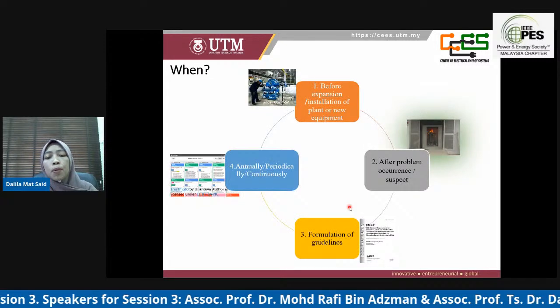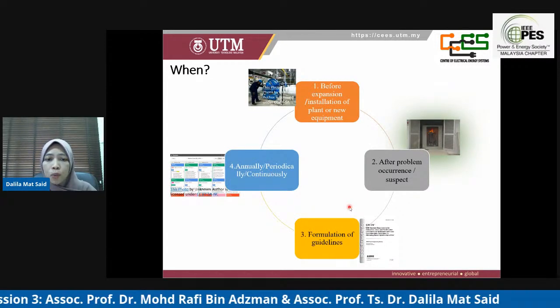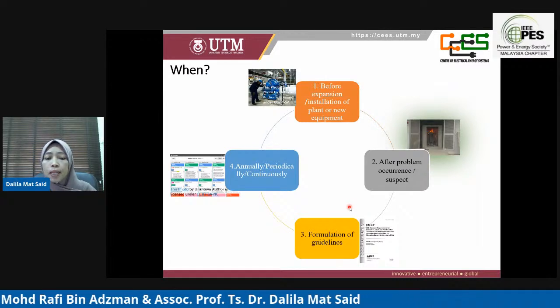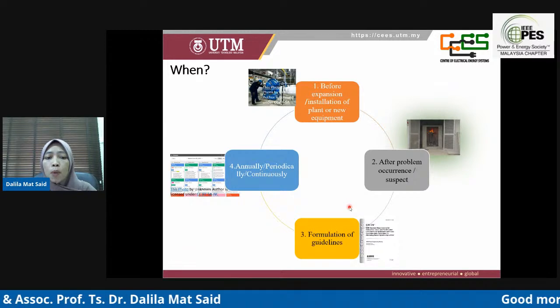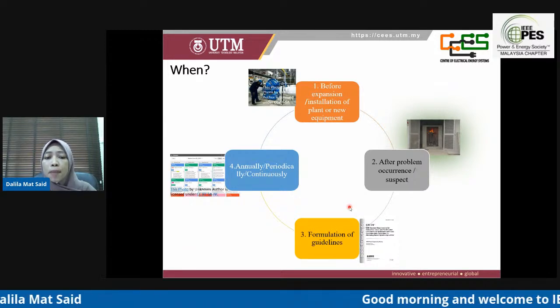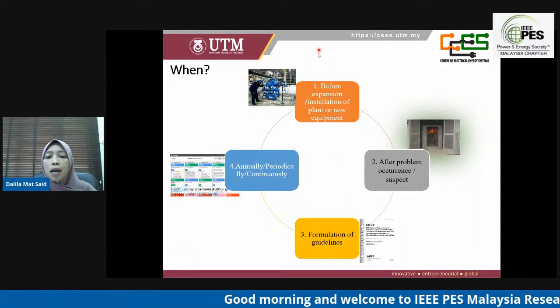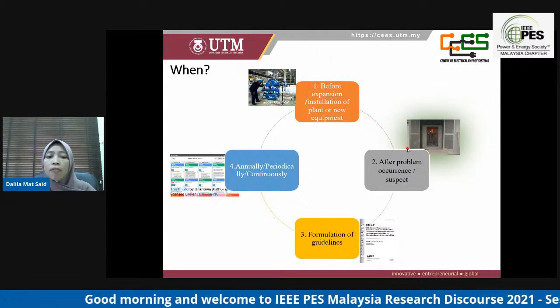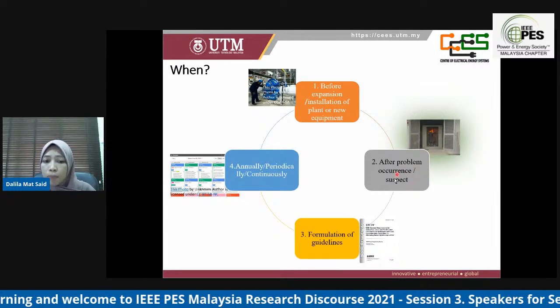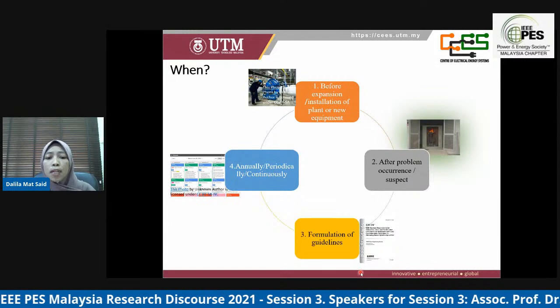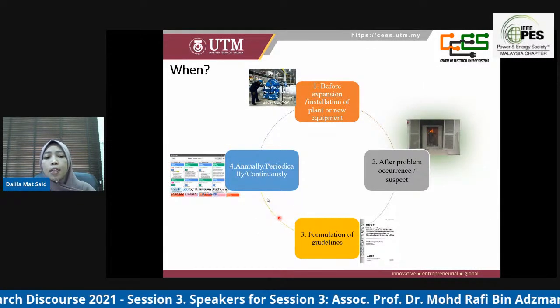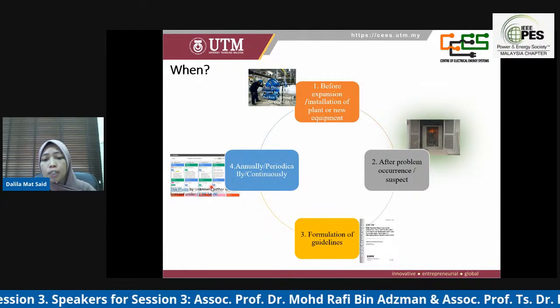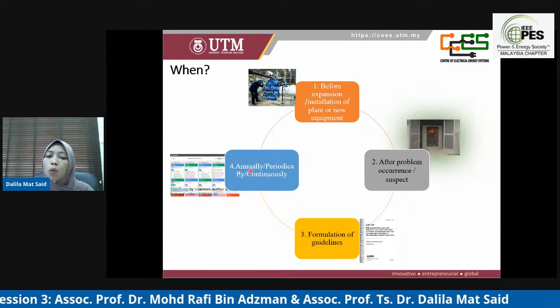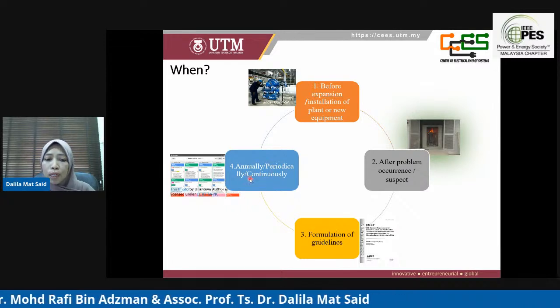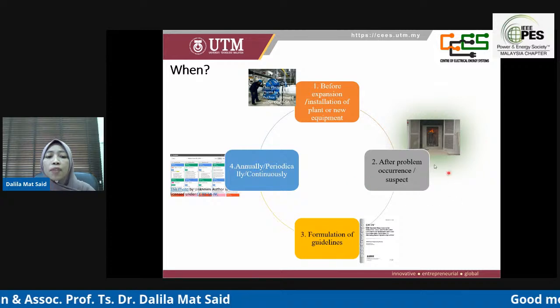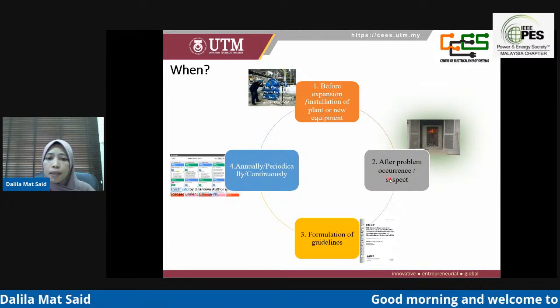Usually, when we want to do a measurement or monitoring, when is the suitable time to monitor? There are 4 suggestions here where we can start to do before any expansion or installation of the equipment, or after the problem occurs or we suspect a problem, for the purpose of formulation of guidelines, and as the utility or electrical supply and some industry and commercial, they will monitor power quality continuously. However, the most requests are after the problem occurrence and suspicion.